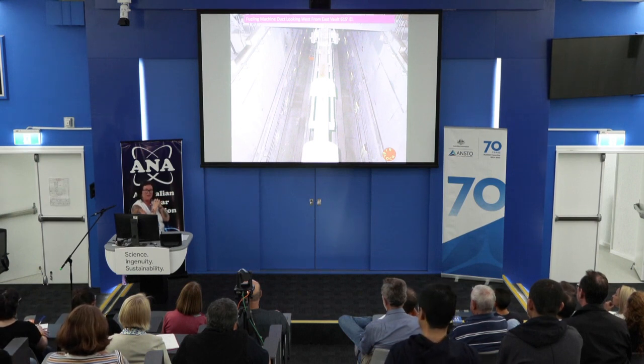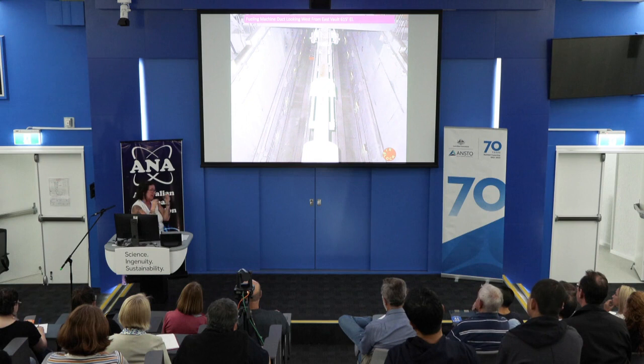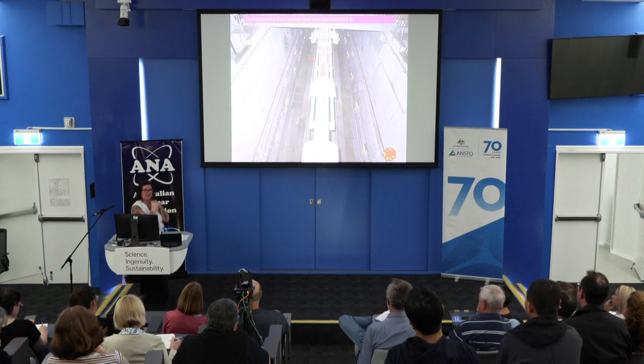So the fuel handlers have to be really well trained, even though it's not a reactor operator position per se. They are very well trained and have a simulator, just like the reactor operators and Unit 0 people do, to make sure they can not only operate the fueling machine safely and correctly, but are prepared to respond to an emergency where, for whatever reason, that bundle wasn't discharged correctly.